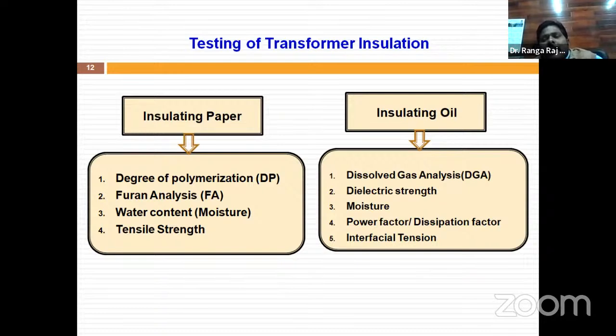What is condition monitoring? The most important part of a transformer is its insulation. The life of an electrical machine is nothing but the life of its insulation. For a transformer, insulation means oil and paper - we have seen the ideal material characteristics. Next we saw aging: what are the various factors which degrade the life of the insulation. Practically, we definitely find aging of insulating material, so we should know the health status frequently - we should not just leave it like that.